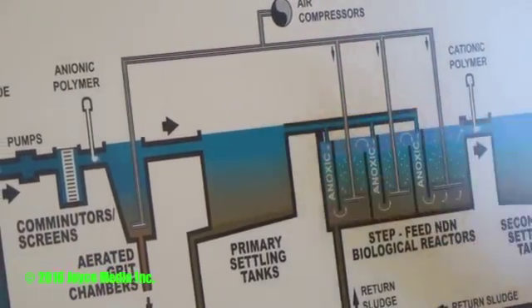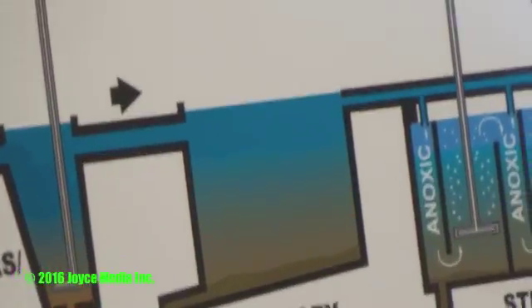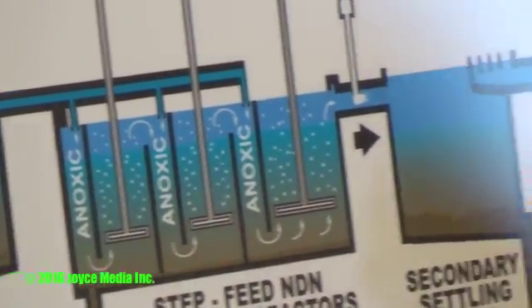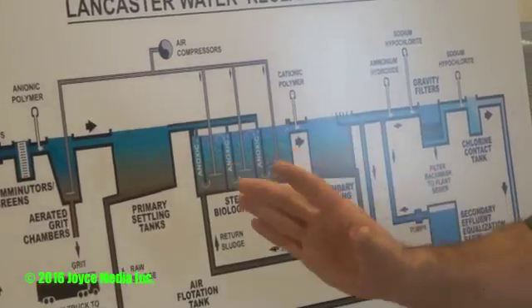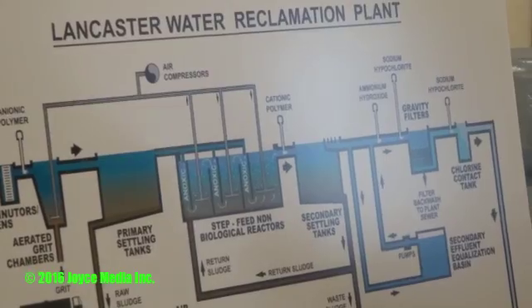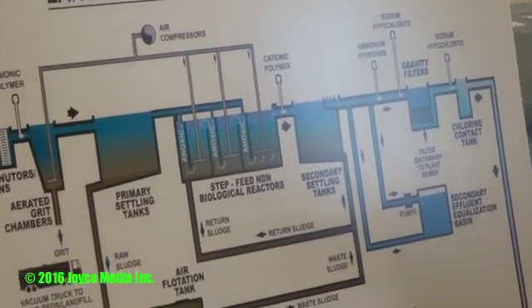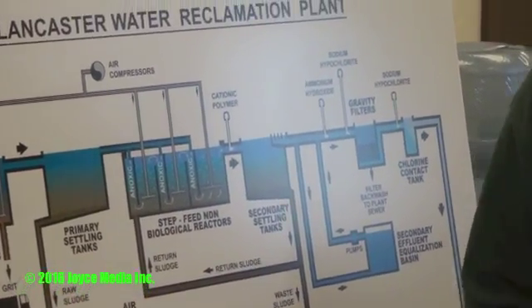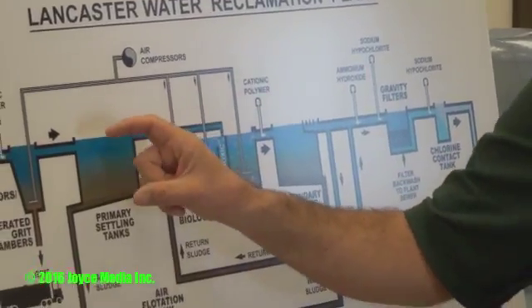What's in the middle — after floating and settling — is our primary effluent, which moves on to our secondary process. We've already removed a lot of suspended solids, which is cheap and easy; floating and settling don't require much energy. We want to remove as much as possible economically to make the highest quality water efficiently.